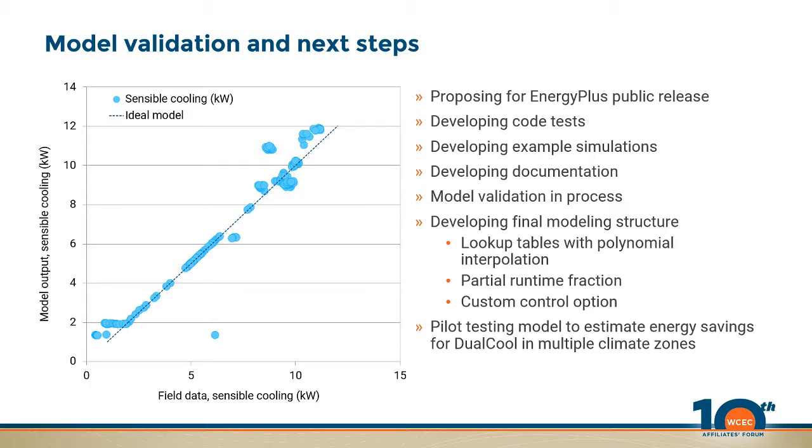Which is what's appropriate. Yeah, the reason I ask is a lot of our equipment now is getting complex. Like a typical rooftop now takes 3 models, not 1 model. So we take 3 equations, and we're finding that tables are a better approach because we can put head pressure control in them, we can put operational in them, so they become non-contiguous tables. So the way you're going is good. Absolutely, and that's one of the reasons we ultimately chose to do lookup tables as well.